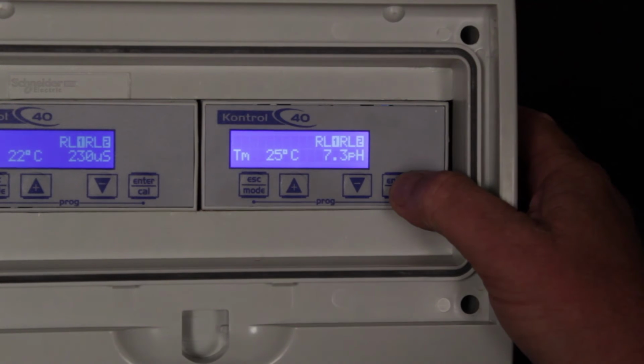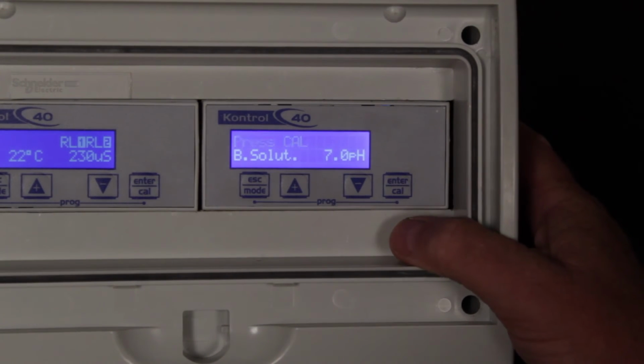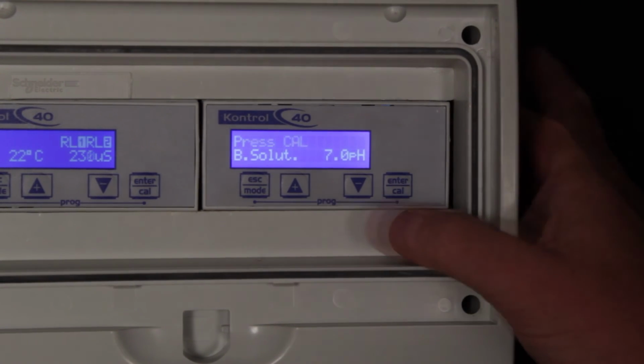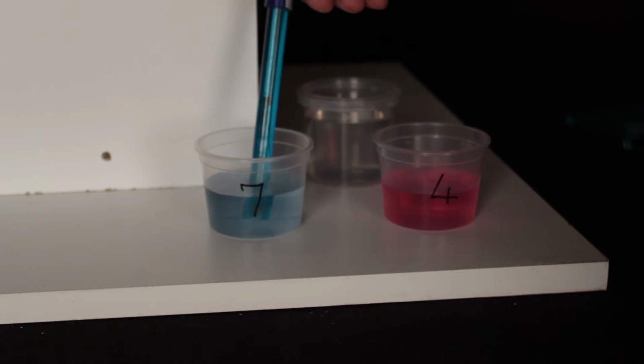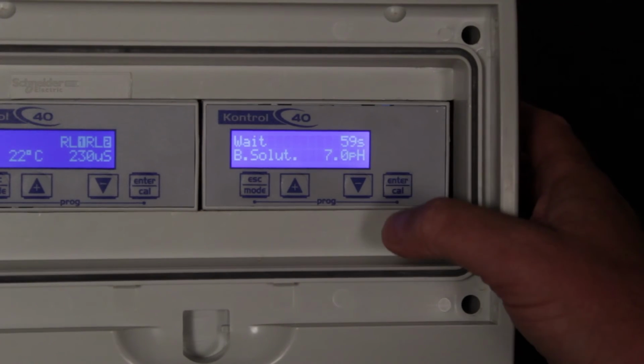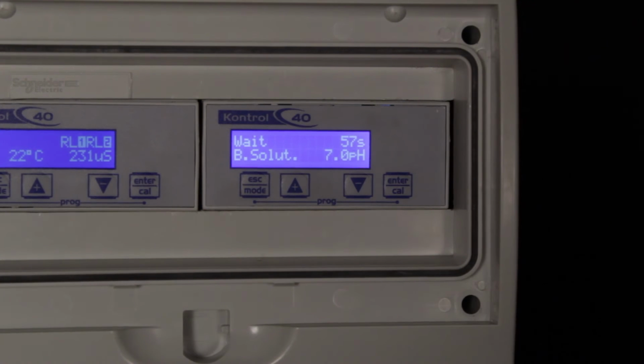In order to calibrate the pH controller, press and hold the calibrate and enter button until the screen changes to calibrate. Now the controller will ask for a buffer solution of 7 pH. Insert the probe into a 7 pH buffer solution and press enter. The controller will now count down for 60 seconds. Please ensure that the probe stays in the buffer solution during this process.